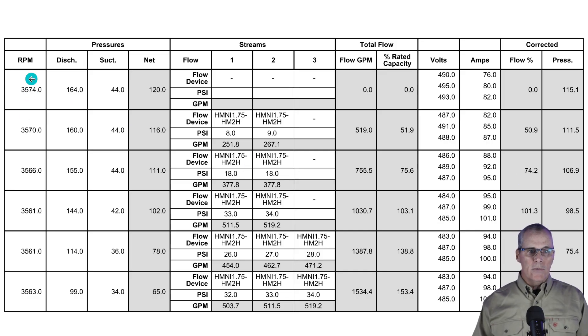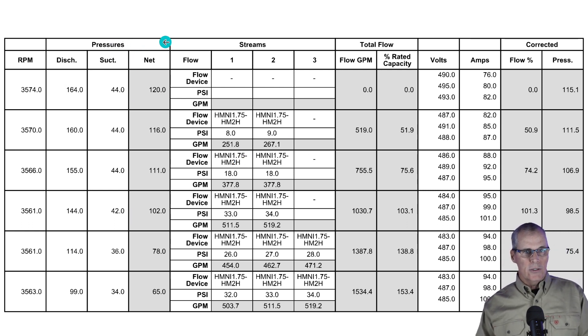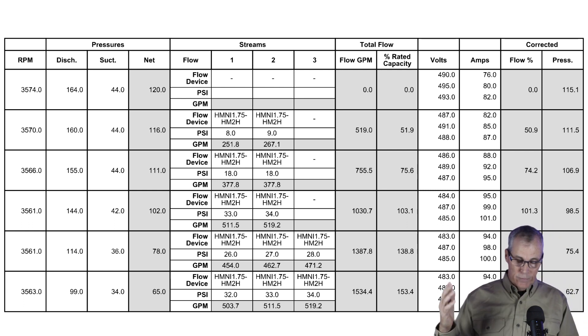Looking at RPMs on the performance test results, let's go across the top of the form: there are the pressures, the streams — that's the flow — and the totals of the streams. Fire pumps generally can flow way more water than fits through one hose, so you use three, four, five, or six hoses depending on their size. The first line is at churn — no flow. Then you record voltage and the corrected flow and pressure. The corrected values are based on the affinity laws, accounting for the difference between the rated speed and the actual speed when running. For example, at 3570 RPM with a net pressure of 116 PSI, with two hoses flowing — 250 GPM out of one and 267 GPM out of the other — that totals to 51% of rated capacity, and then we correct it.